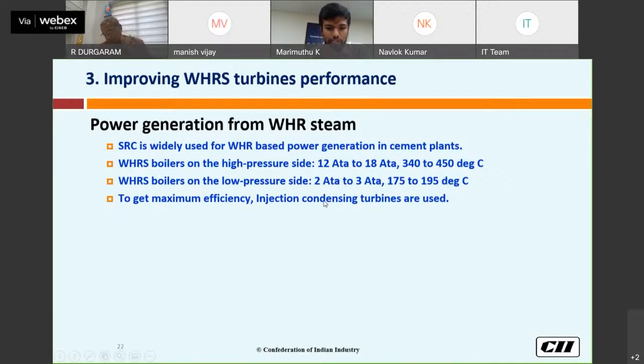Generally for a low pressure area, to get maximum efficiency, injection type condensing turbines are used. In WHR, we get a pressure of around 12 to 18 atta, at 340 to 450 degrees.